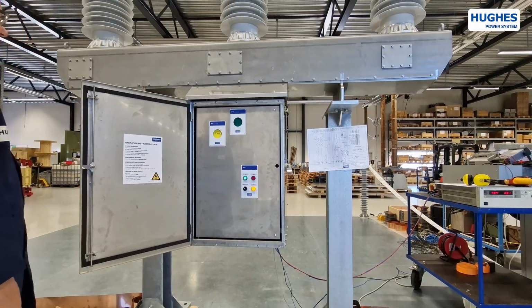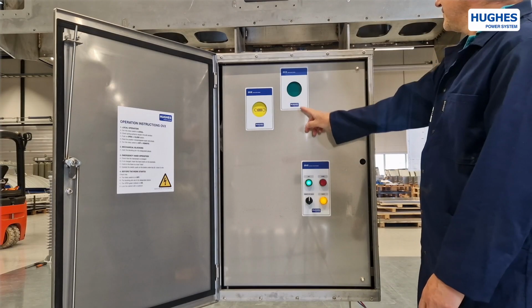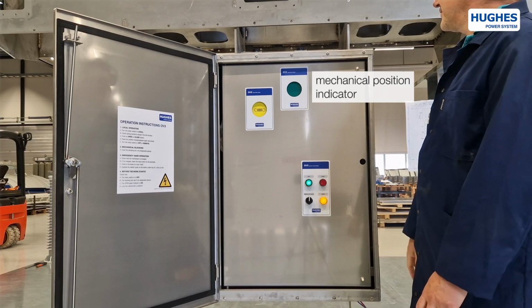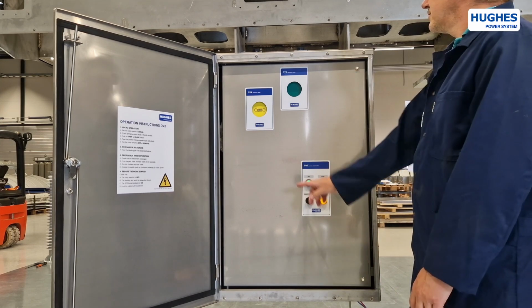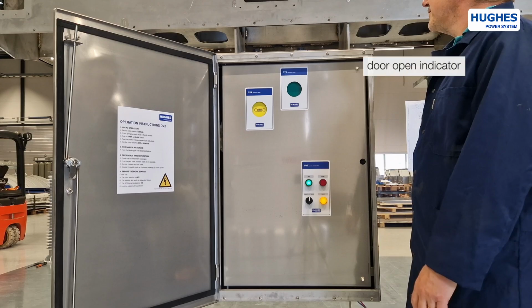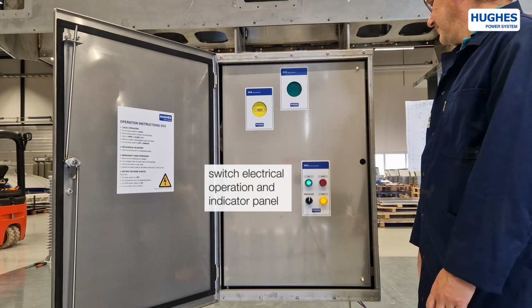The internal door contains the following panels. This panel is the switch main mechanical position indicator. Red indicates that the switch is closed and green that the switch is tripped. The next panel with the yellow window is the mechanical spring charge indicator. It shows the status of the stored energy mechanism. The push button in the upper right corner is the door open indicator to the SCADA system as well as the lamp on function. The third panel is the switch electrical operation and indicator panel.